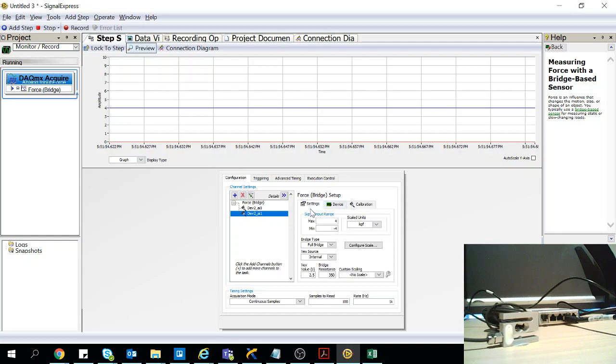From this video, you can see that you can add multiple channels to your load cell measurements. The configurations might inherit default values from the previous channel, but they are actually independent of one another. The only thing to bear in mind is that the excitation value has to be the same. The bridge resistance can be different, but that's about it.